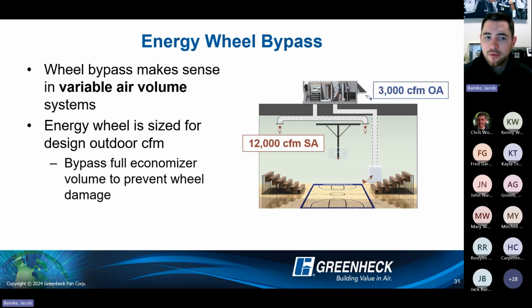So that's typically how that wheel is sized. In bypass or in economizer, now we actually have 12,000 CFM potentially coming through that wheel. Well, that wheel might not be sized to handle that full amount. That is when you need a bypass damper so you can prevent wheel damage. In those DOAS applications, you already have a wheel sized for that 100% outside air. So that's where it makes sense to just size it as large as possible to get the most effectiveness and the least amount of pressure drop during normal operation.